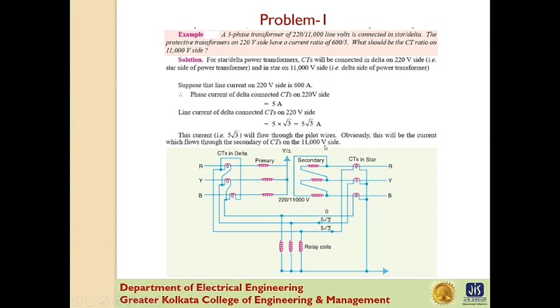Now for the line current of the delta connected CTs on the 220 volt side, we all know that phase current into root 3 is the line current. So 5 into root 3 is the line current of the delta connected CTs on the 220 volt side. So this 5 into root 3 will flow through the pilot wire, and obviously this will be the current which flows through the secondary of the CTs on the 11,000 volt side. So the secondary of the CTs on the 11,000 volt side is 5 into root 3 ampere. Now we find out the primary current of the CTs on the 11,000 side.